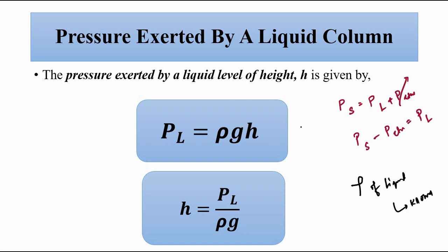So when we get the liquid column pressure, we get the height of the liquid using this relationship. We get the liquid column pressure from the sensor by subtracting the atmospheric pressure from the sensor reading, and since the density and the acceleration due to gravity are known, h is equal to P_L by rho g. This is when the lid is open. When the lid is closed, the sensor reading directly gives us the liquid column pressure, because the atmospheric pressure in that case is 0. In the other case, we have to subtract the atmospheric pressure from the sensor reading. From this we get the height or the level of the liquid in the container or the tube. So this is the basic relationship.